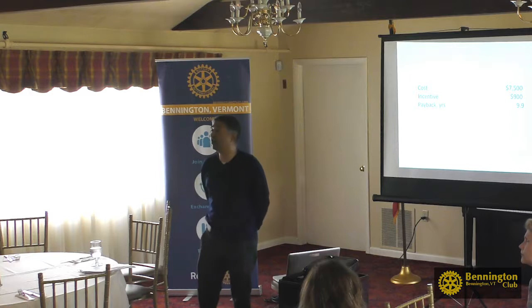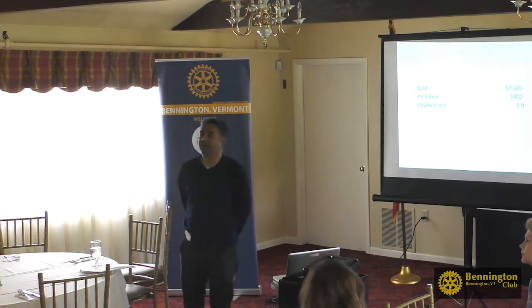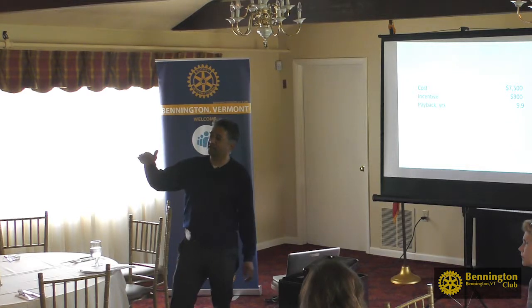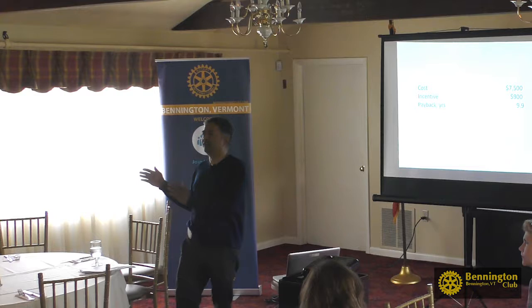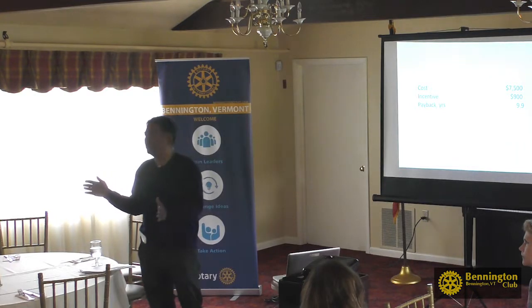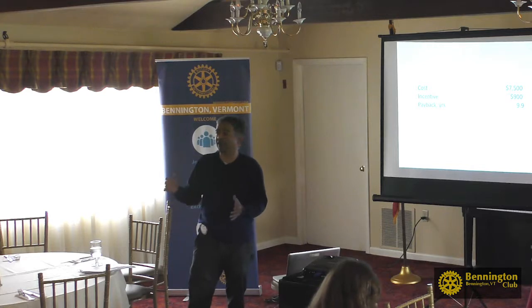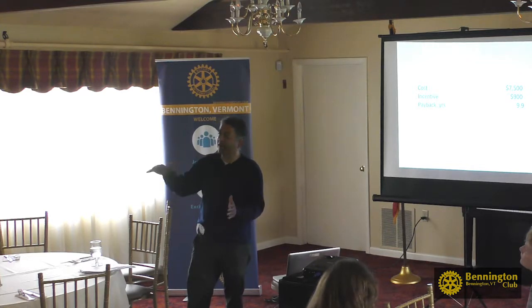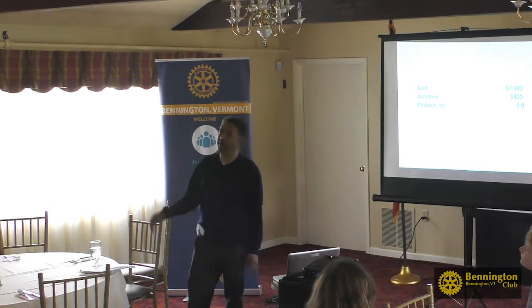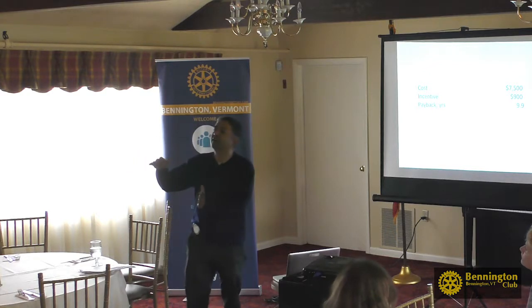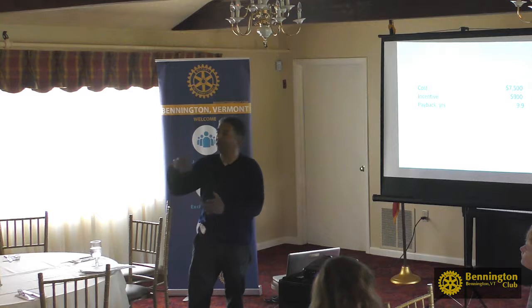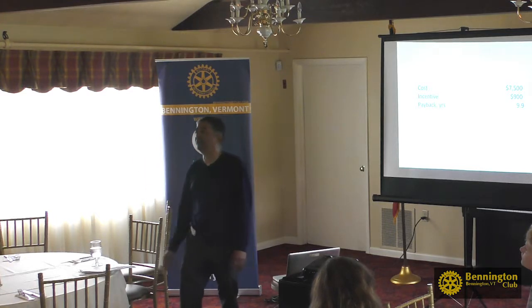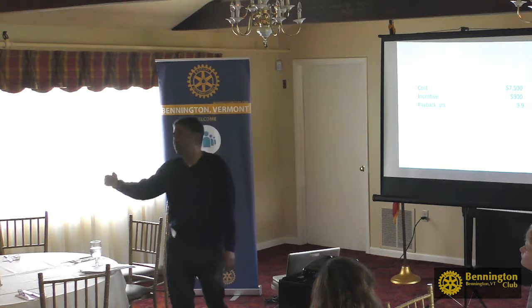Right, when it's very cold. The temperature transition where that happens is usually around 5 degrees Fahrenheit or so. Between 5 and minus 20, think about how many hours of the year that is — probably 200 to 300 hours a year, maybe more. Looking at the bin data for dry bulb temperatures, it's probably around 300 to 400 hours in that range. So it's not a huge amount of time that your system becomes pure electric resistance, but those hours do add up to large electric bills.